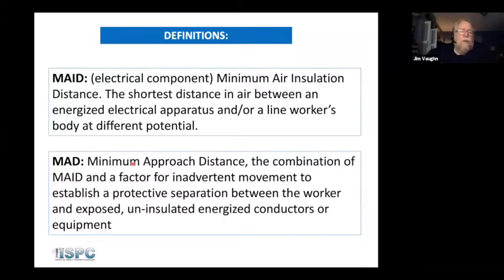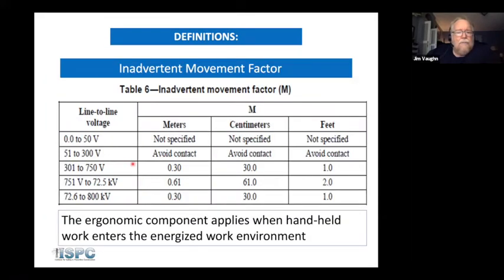And in distribution work up to 72 kV, that inadvertent movement is 2 feet added to the MAID, and that's what creates your MAD in distribution. So here's an example of this inadvertent movement factor from Table 6 in the OSHA standard, and you'll also find this in the IEEE standards. And you see right here, 750 volts to 72 kV, 2 feet. Above 72 to 800 kV, it's 1 foot.